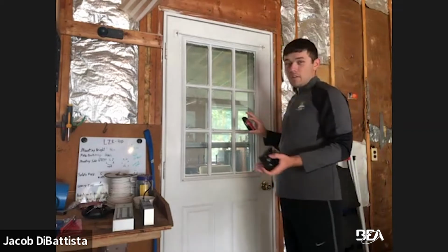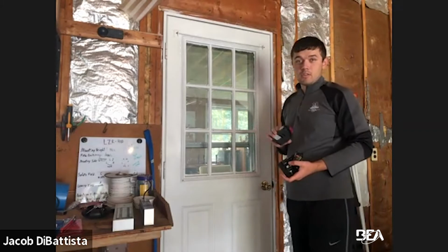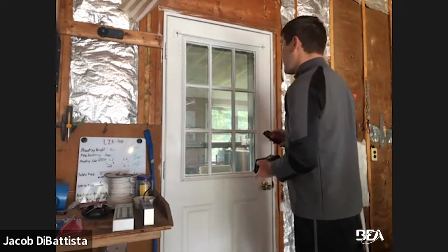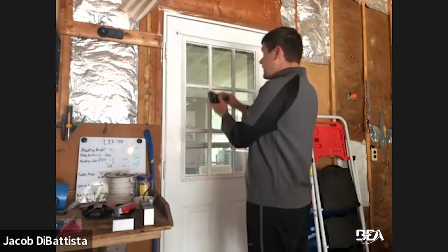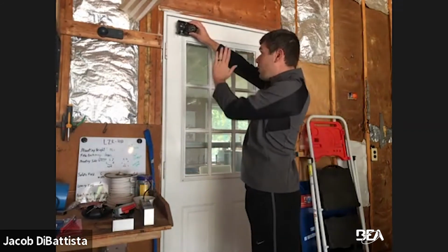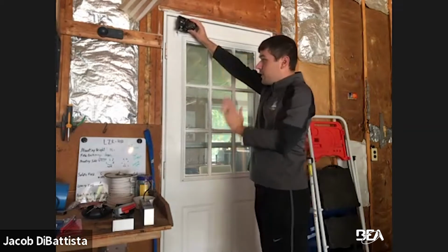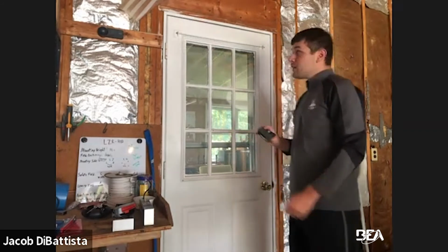Installation instructions for all these sensors, we do have Tech Time Lives for a majority of these, and we do have other videos on the YouTube channel, so we go more in depth in those. But to stick with the point, FLATSCAN 3D up here is going to project 4 curtains out. So 1, 2, 3, 4. And the distance between each curtain depends on the height.